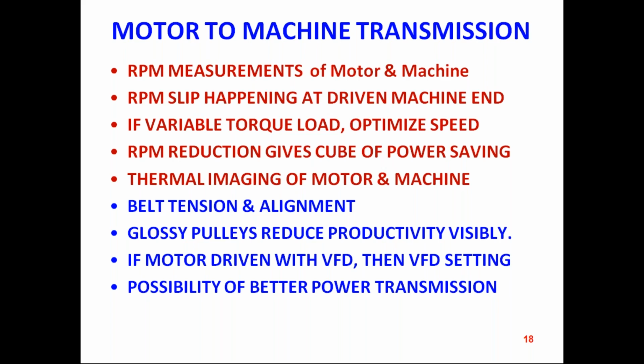A blower or a fan spec is different. A VFD is a facilitator for the given blower to achieve the best efficiency point in the fan performance curve. I repeat again, this is a critical area which we can address, because it is a combination of academicians plus the industry. Your college is doing an excellent job in a lot of sugar and textile mills. Thanks to our Dr. Sanjay Kote. He used to tell us how much energy intra-industry interaction you are doing from the college. You concentrate on the basic measurements, especially on each and every machine.